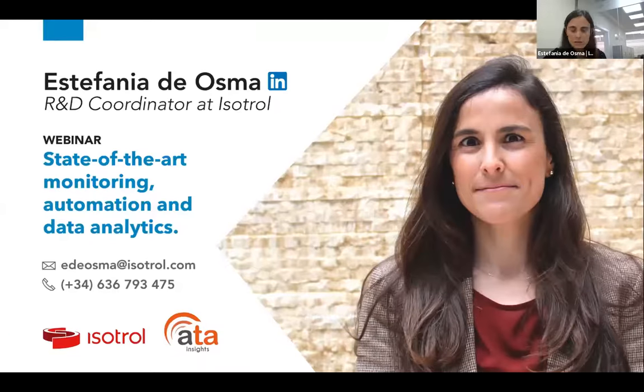Okay. May I add something? I completely agree that it's important to have information on the key aspects, and just to put the strong points from our experience: there are different signals that contribute a lot to identifying problems in the PV plant, for example the temperatures in the inverter, the ventilation, the air cooling that you have there. Having information at inverter level regarding temperature brings a lot of information that may help us to identify problems.